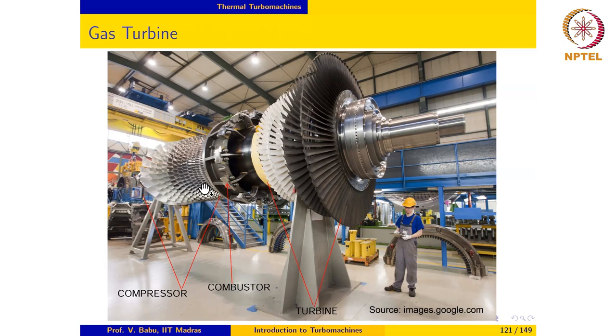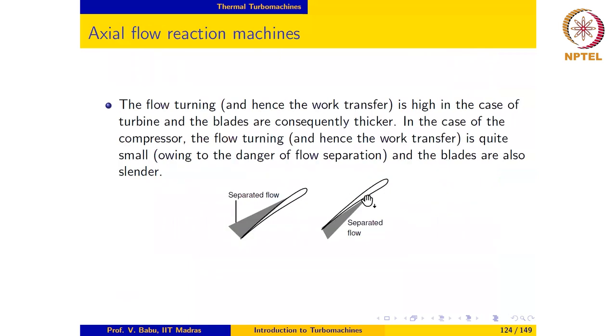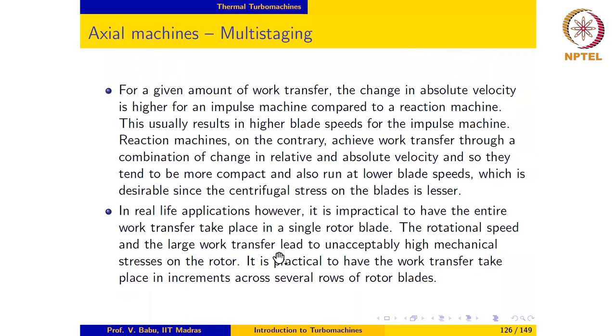Probably only one or two turbine stages drive the entire 12 to 15 compressor stages, while the remaining turbine stages convert combustion gas enthalpy into work to run the generator. By having multiple rotor blades, we can reduce work transfer in each rotor and consequently bring down rotational speed, which reduces mechanical stresses on the rotor. This is what is done in practical installations.